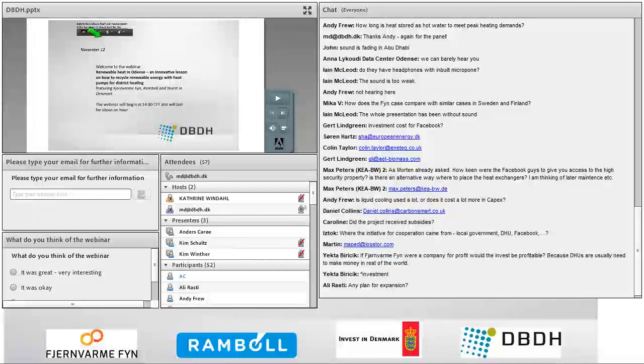Good. There's also a question from Claude. I'll just read it out because he sets this COP value at 4.8 to 5.2. Is that for each of the heat pumps, or is it for the group of 3 heat pumps working in series? What is your comment to that? So the COP of around 5 is for the heat pumps overall, but also for each single group. For the individual heat pump units, some of them are above 5 COP and some of them are below, but the average will be around 5.